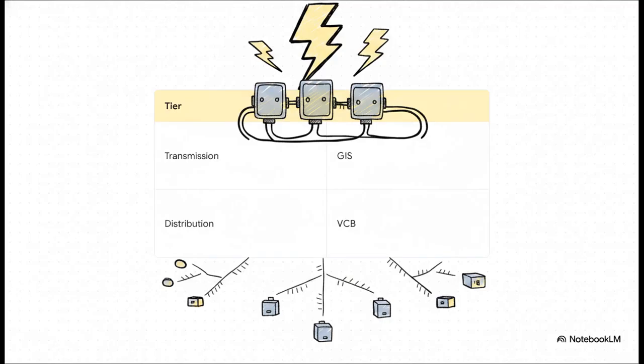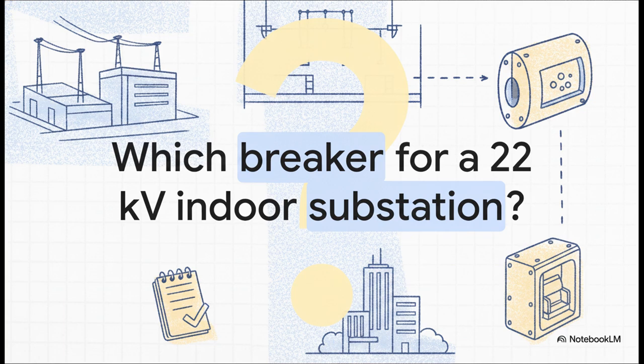And that brings us to the definitive voltage ladder mapping. If you're working on the grid, you really want to burn this into your memory. Here's the golden rule. At the massive transmission tiers at the very top, so 400, 230, and 66 kilovolts, the system relies strictly on gas-insulated switchgear. But the very second you drop down to the distribution tiers at the bottom, the 22 kilovolt and 6.6 kilovolt networks that branch out into neighborhoods and industrial parks, vacuum circuit breakers take over completely. This is the official assignment matrix for Singapore's electrical grid. No exceptions.